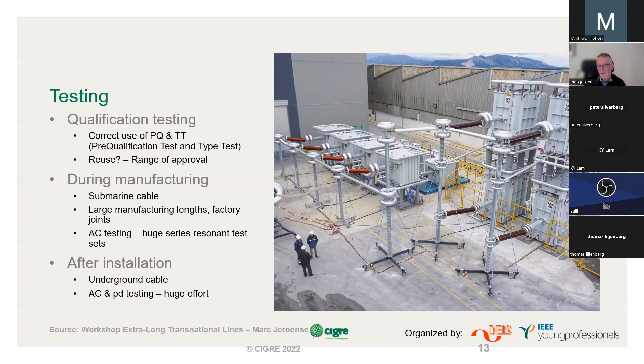I just want to mention briefly that many cable systems, if not all, are using integrated fiber optics. So the armor wire or maybe a copper screen wire in the underground cable is removed and replaced by a fiber optic in a metallic tube.